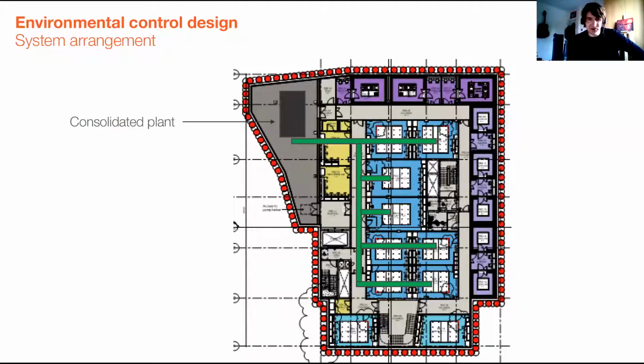So this is a floor plan, and because of the vibration control, which we'll come on to in a bit, we needed to keep all rotating plant outside of the general lab area. So we had a consolidated single air handling unit in the plant room, and then a network of ducts from that plant room, which Rebecca already mentioned.